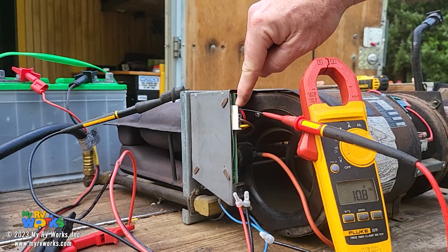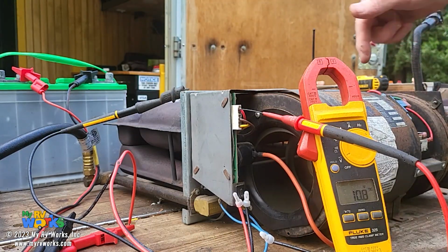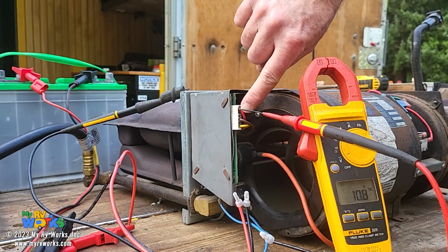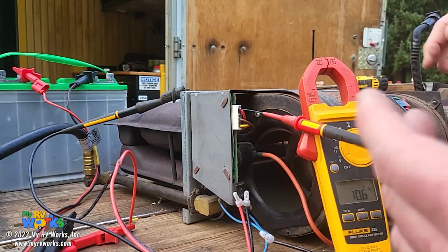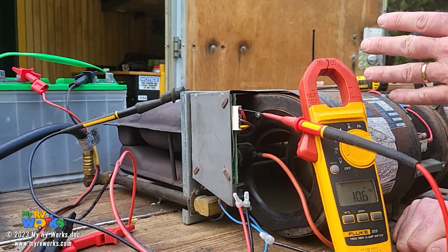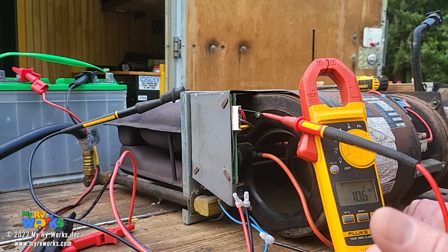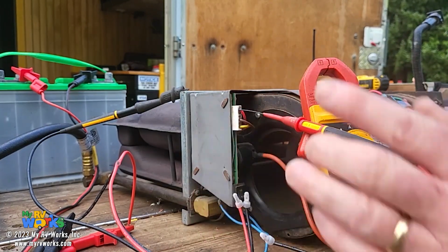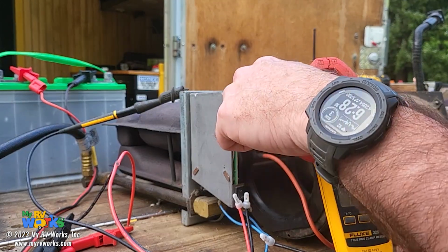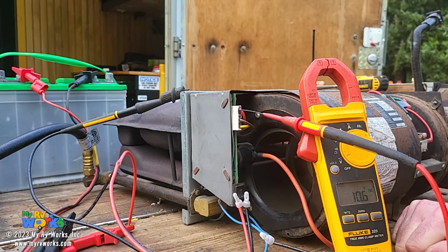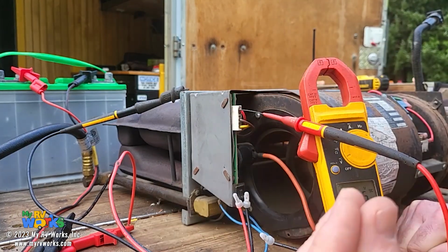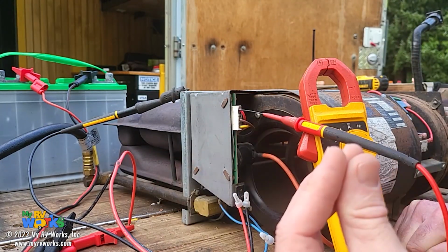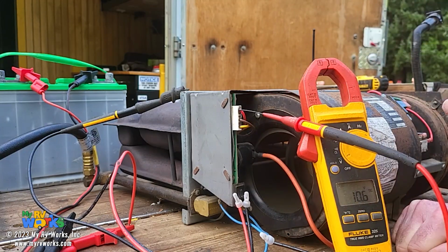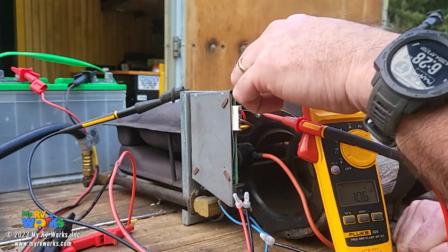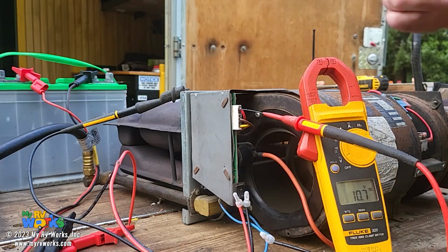Our red wire is telling us the high temperature switch and sail switch signal, so therefore, in order for there to be voltage on this red wire, it started back up again. And I remember earlier I said that sometimes it won't. So if I'm diagnosing an intermittent problem on a furnace, and I'm looking at this red wire, and that voltage comes and goes, and coinciding with it coming and going, my furnace extinguishes and ignites, then the problem is with that red wire -- the sail switch, the high temperature switch, or a call for heat signal. That's what I wanted to show you guys.